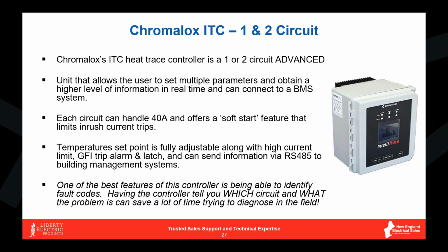What I do like about this particular controller is that it does offer a soft start feature as well, which will prevent you from spiking that inrush current on your voltage and potentially tripping GFI breakers. So, if anything, there are some really nice features and benefits to these advanced controllers, but the one thing that these really are susceptible to are power quality issues. And we're going to talk about that in a second too.